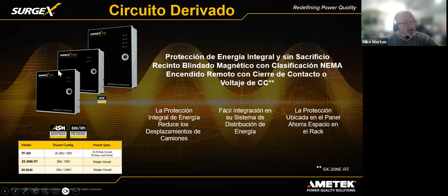The middle device that you see here is a single 20-amp circuit in and a single 20-amp circuit out. This one does have contact closure, so you can hardwire a switch or perhaps go to a processing device, some kind of a control system, to control the on-off as well from this location. And then we also have a 240 version. The reason for that is many projectors, or some projectors, I should say, are coming out in the 240 version, and we want to be able to give you that capability as well. That's a single 20 amp in, 20 amp out at 240. These are all steel NEMA enclosures and completely approved.